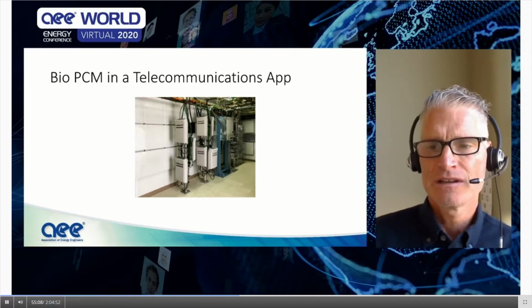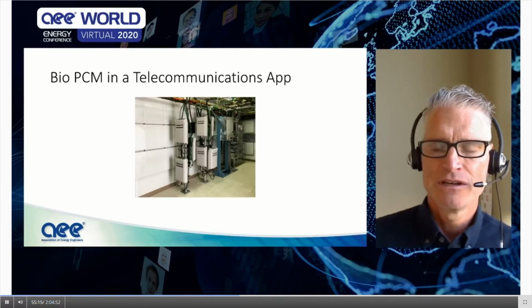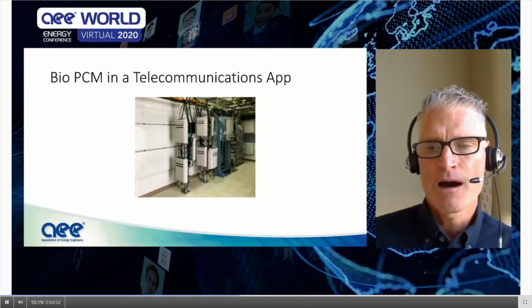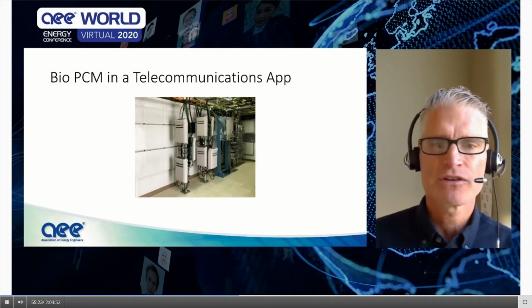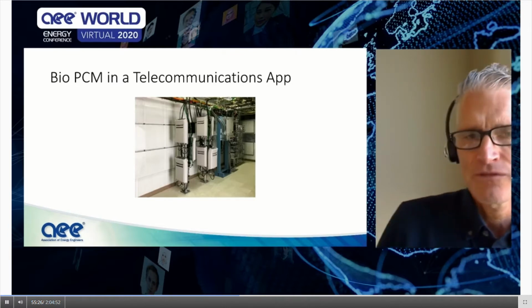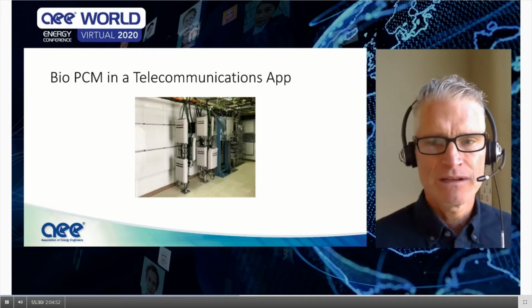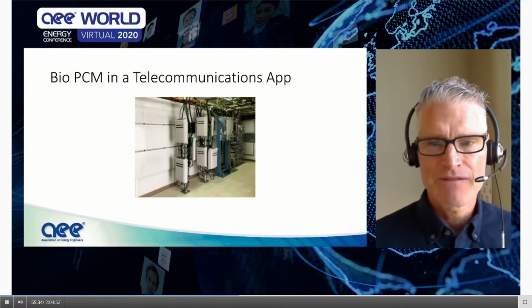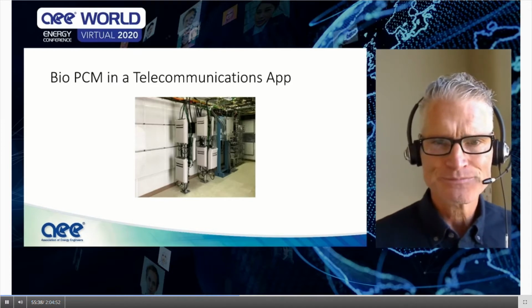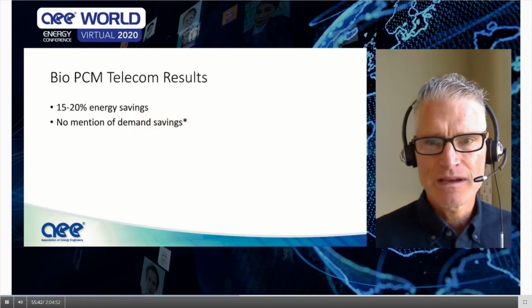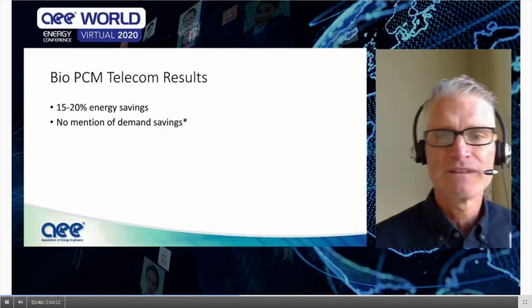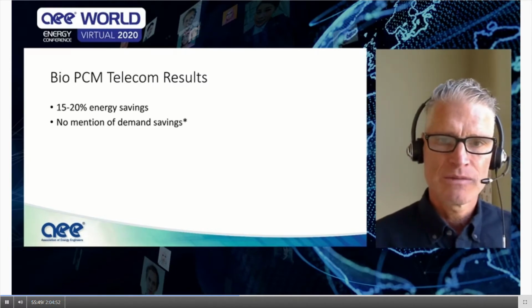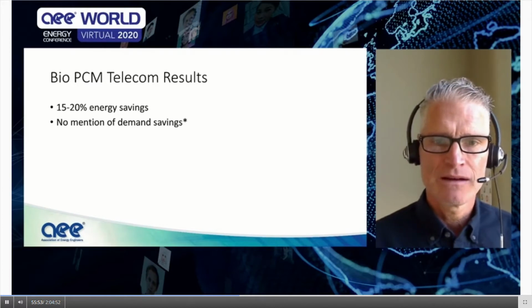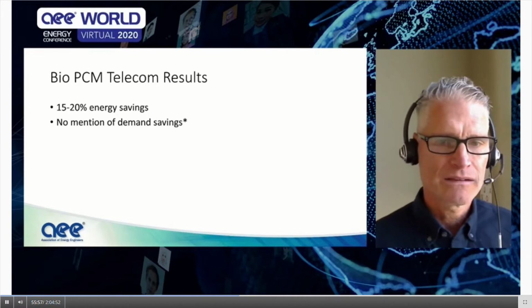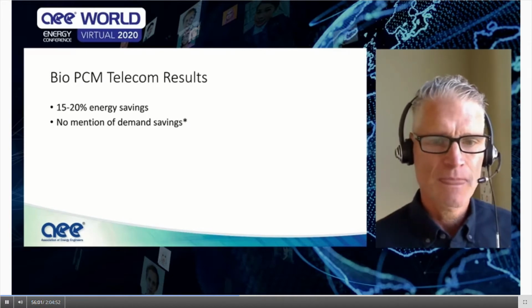Like the freezer condition, this is a really good application for PCMs because the equipment doesn't care about a few degrees of temperature change. In this case, the space was 78 degrees. It probably needs to be cooled to 75 degrees to freeze the PCM when it needs to be frozen or charged. And then it's melted maybe at 80 degrees. The equipment doesn't care whether it's 80 degrees or 75 degrees in the space. So it's a great application for that. The energy savings for these applications were 15 to 20%. There was no mention of demand savings, probably because these are really small facilities and there's no demand component to their bill. But they were looking at this for hundreds of these shelters across the country.